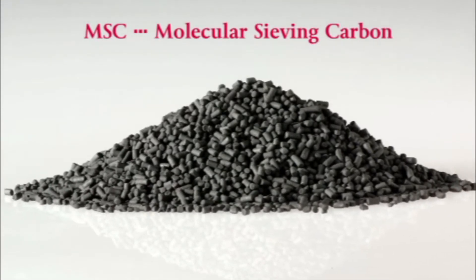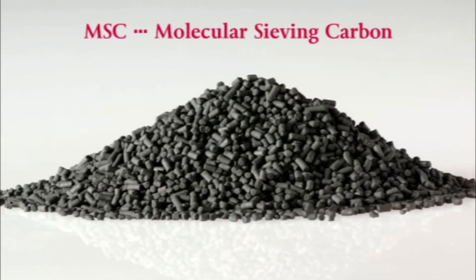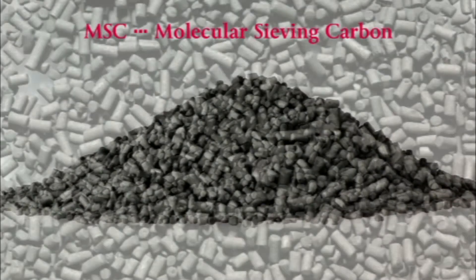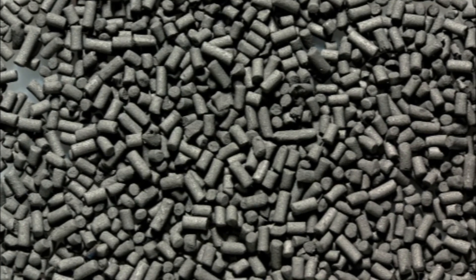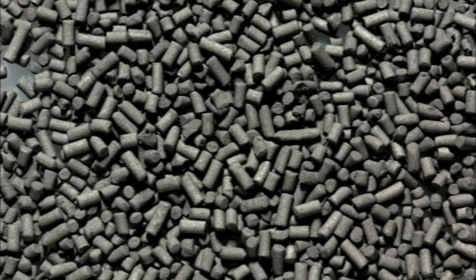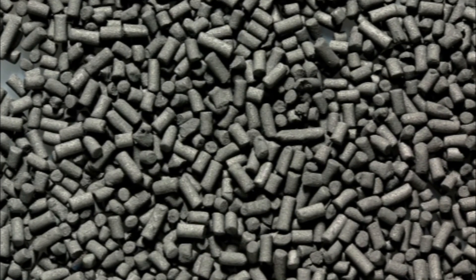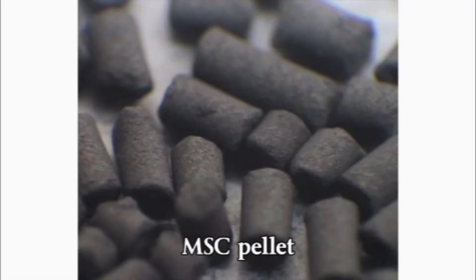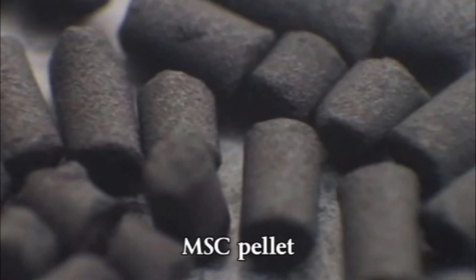In Mayakawa's PSA system, molecular sieving carbon, or MSC, is used as adsorbents. Palm shell or coke used to be used as adsorbents in conventional PSA systems. However, Mayakawa utilizes new carbon adsorbents made from special phenol resin. The MSC used in our PSA system is cylindrical, one millimeter in diameter and two to five millimeters in length.